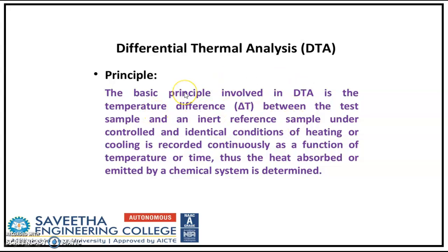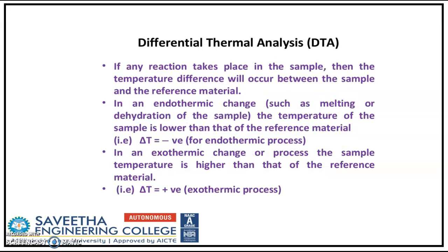So the main principle involved in DTA is the temperature difference between the test sample and an inert sample. It is controlled by heating or cooling, and is recorded continuously as a function of temperature or time. Thus, the heat absorbed or emitted by a chemical system is determined. So, this is the basic principle of differential thermal analysis. Mainly, it records the temperature difference between the test sample and an inert sample.